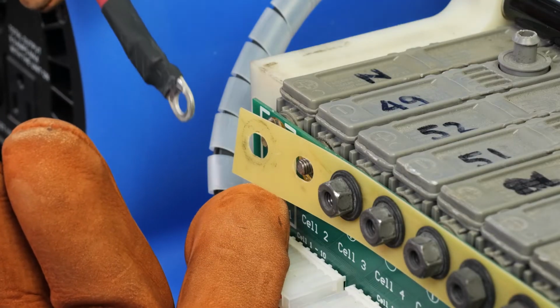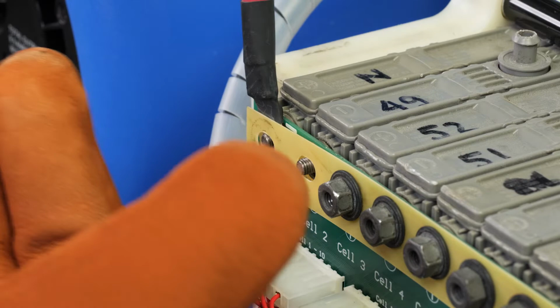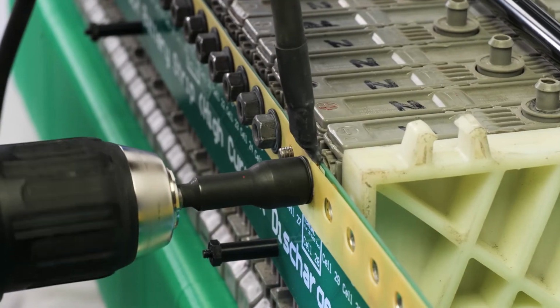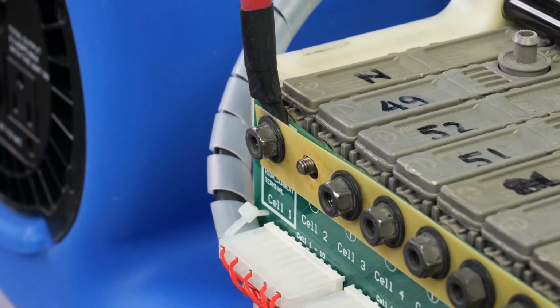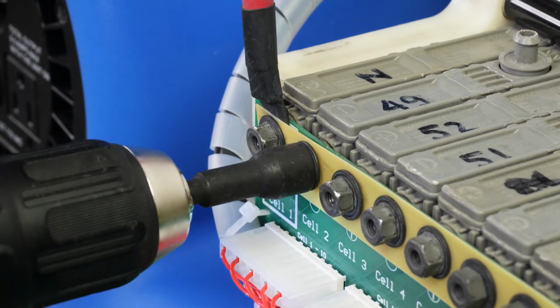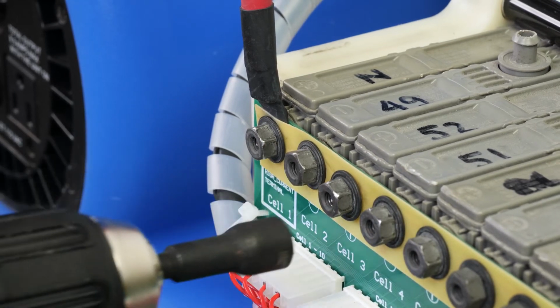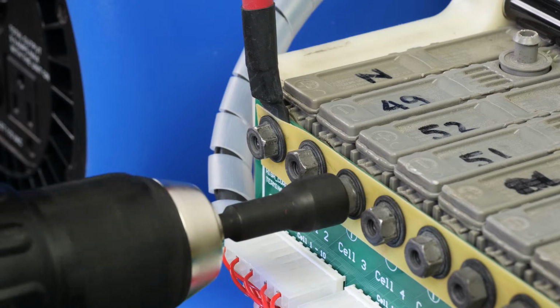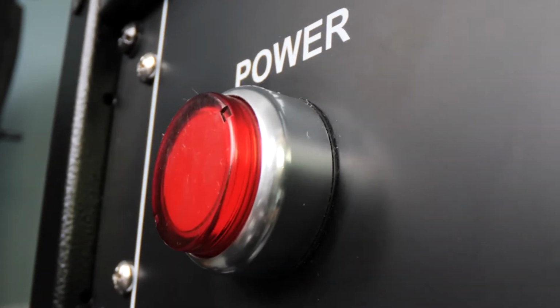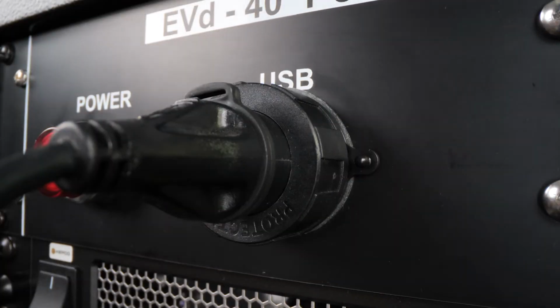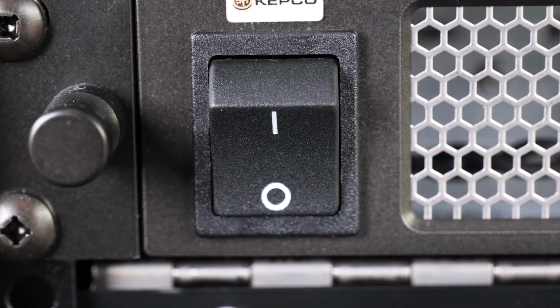Now we will attach the high voltage leads. The red cable is positive and the black cable is negative. They will both go on one side of the harness only. Refer to the markings on the boards and always double check your connections. You can now turn on the EVd40 and connect to the laptop. Make sure that the charging power supply here is off.